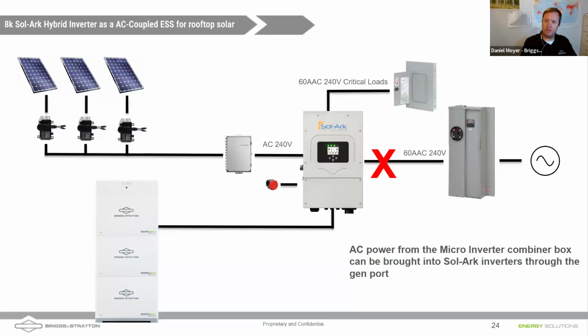One interesting thing on this slide, Nathan, is that we are potentially not only taking 60 amps from the grid, but we could push 60 amps back into that load center. And a lot of times these panels are 200 amps with a 200 amp bus.